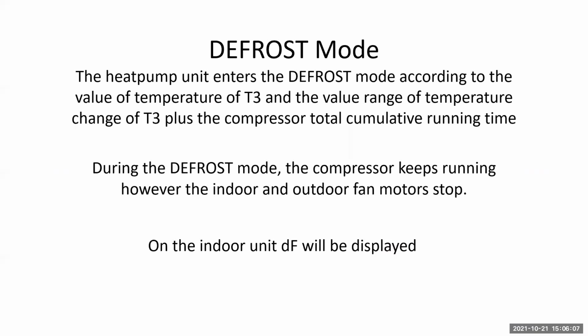The unit looks at the temperature of the T3 sensor, which is the condenser coil sensor, and the value range of the temperature change. Then the compressor takes that into account and does a total cumulative runtime. And that's how it determines how long the defrost is going to take, and when it goes into defrost.